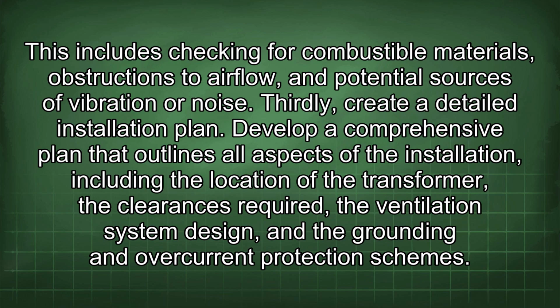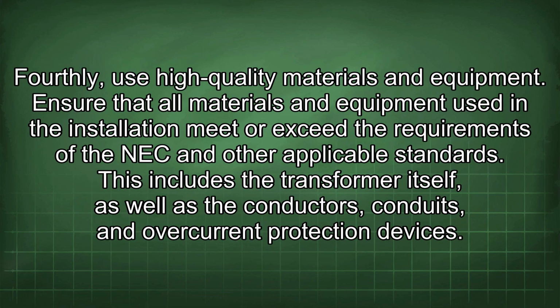Thirdly, create a detailed installation plan. Develop a comprehensive plan that outlines all aspects of the installation, including the location of the transformer, the clearances required, the ventilation system design, and the grounding and overcurrent protection schemes. Fourthly, use high-quality materials and equipment. Ensure that all materials and equipment used in the installation meet or exceed the requirements of the NEC and other applicable standards. This includes the transformer itself, as well as the conductors, conduits, and overcurrent protection devices.